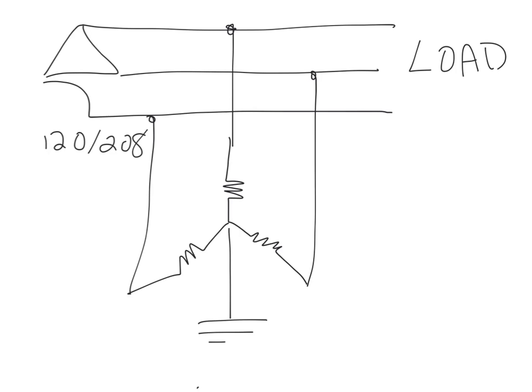Now your ground detection device is this Y-connected portion right here, so it's important to understand that's a device. You can see up top here we have the secondary of a distribution transformer of some kind and it's connected in Delta. That means it's an ungrounded system.